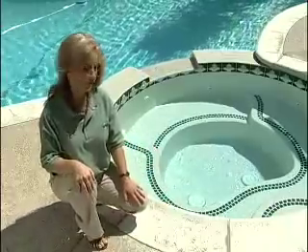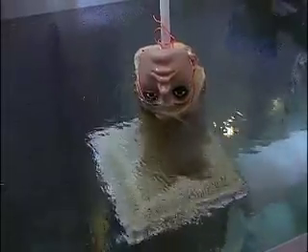Unfortunately, accidents involving swimming pool suction happen every year. Children and adults alike can get pulled under and trapped under the water, often leading to injury or even death. This testing apparatus simulates what might happen if someone's hair were to be drawn into the suction fitting. Water is pumped through while technicians use actual human hair, attached to a handle and a mannequin fitted with a gauge, to measure the amount of pressure exerted by the suction fitting. Five or fewer pounds of pressure receives a passing grade, while anything greater fails. Additionally, a simulated human torso apparatus is now also required.